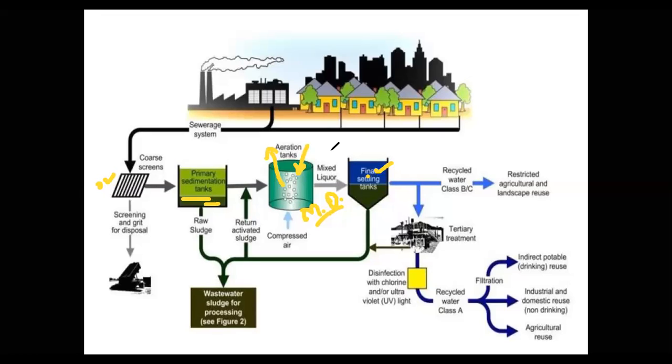They will be in a floating or suspended position. If we add some coagulants, that coagulant will neutralize the charge of the particles. Because of neutralization of charges, they will come together, and once together, they convert into a floc, a larger size particle. Once it is converted into larger size particles, it will be possible to settle down by gravity in a secondary clarifier.